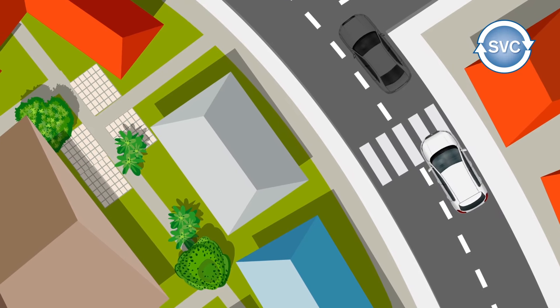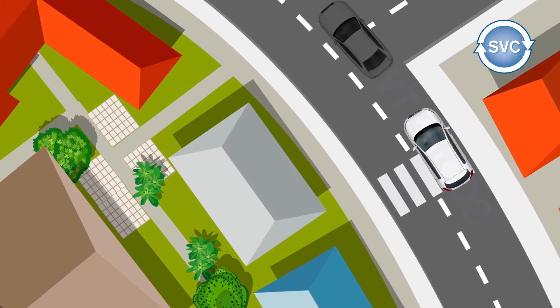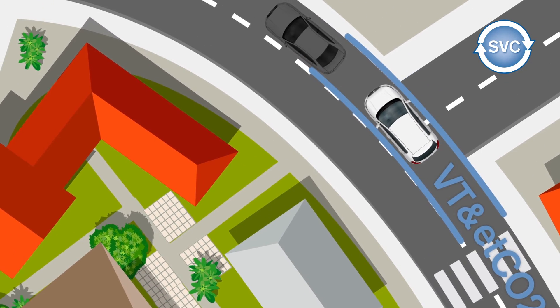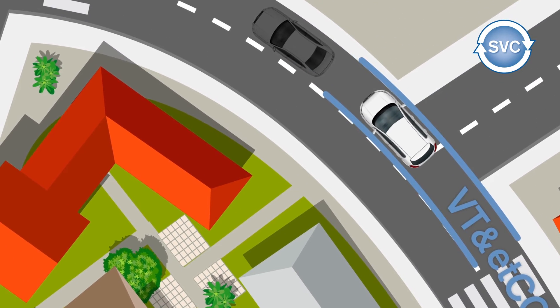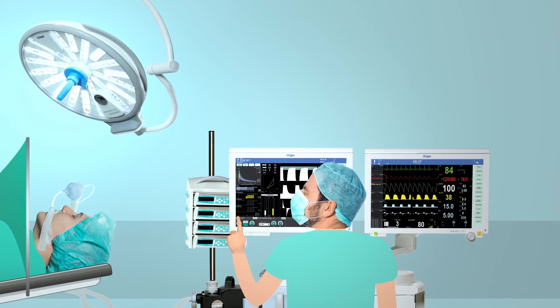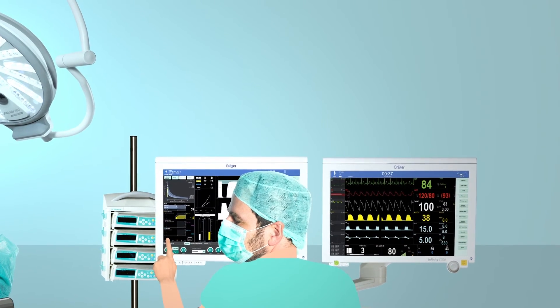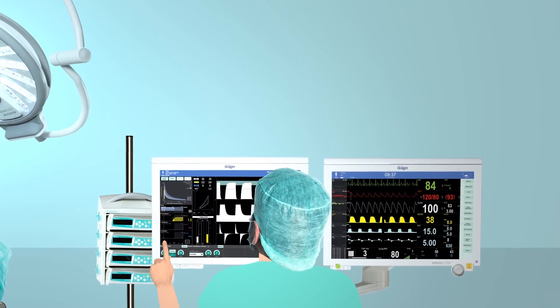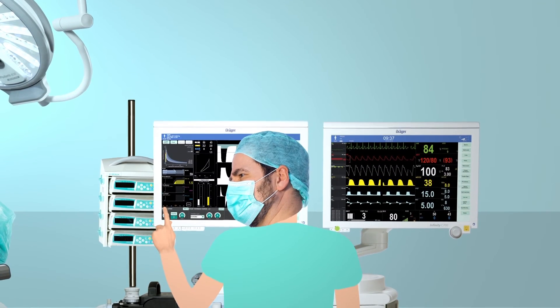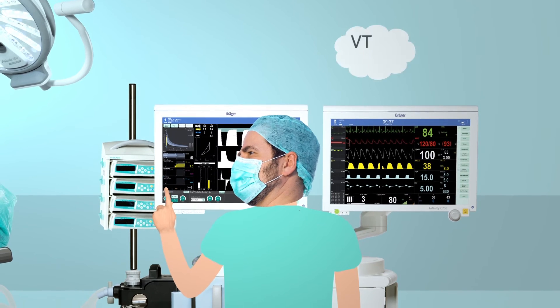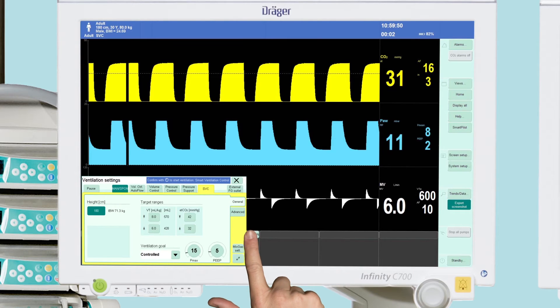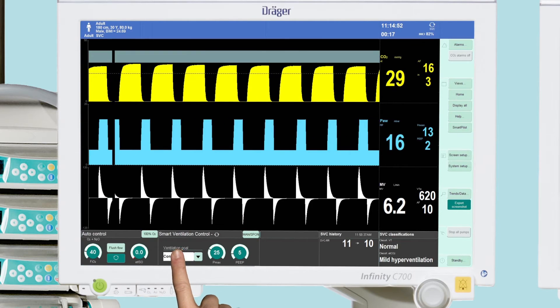How does it work? Similar to a lane assist system, Dr. Miller defines his route — which is the VT and end tidal CO2 target values. The SVC ensures that this route is followed. Clinically, it looks like this: the patient is given a relaxant. Dr. Miller starts Smart Ventilation Control and defines the target areas — end tidal CO2 at 4.3 to 5.7%, and VT at 6 to 9 milliliters. Dr. Miller then chooses smart ventilation control and sets the respiratory goal to controlled ventilation.